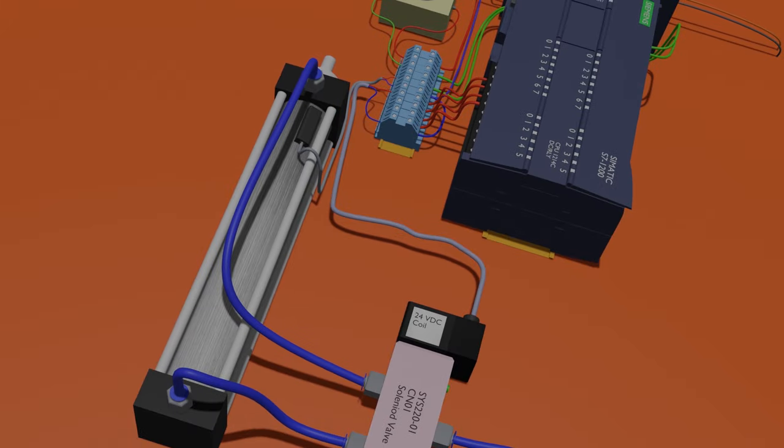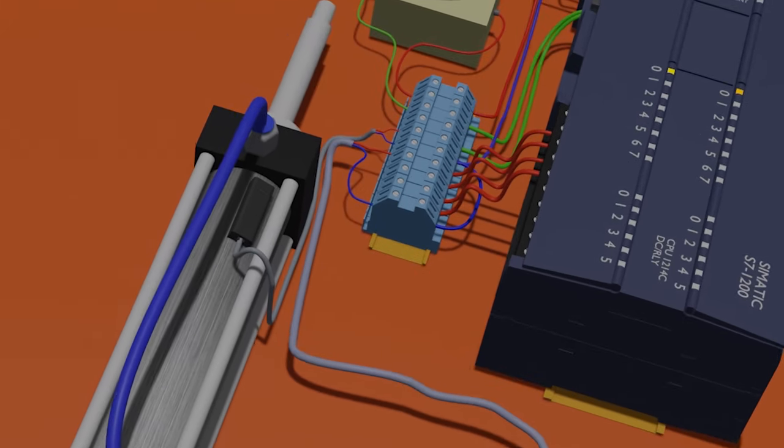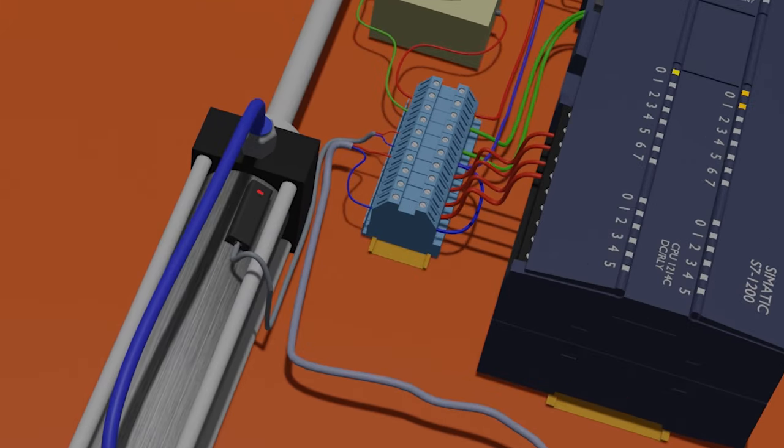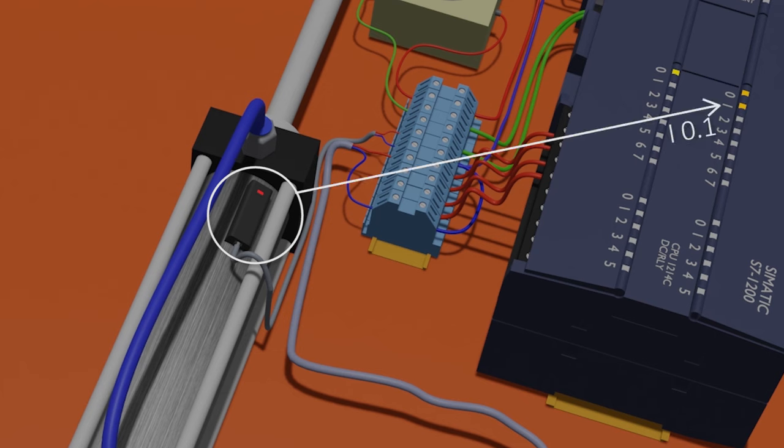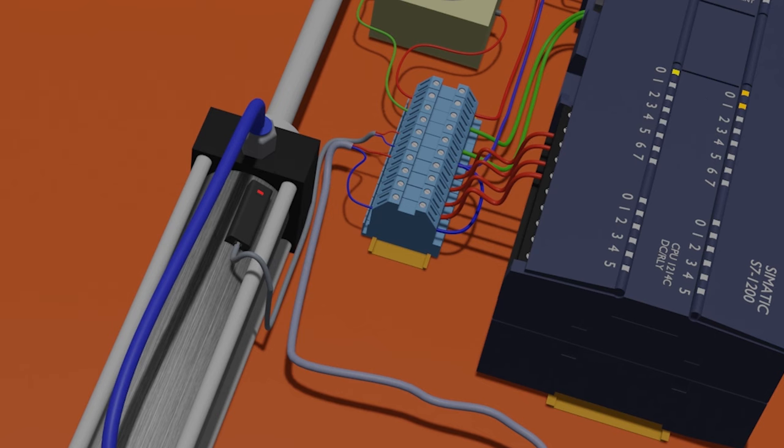We have installed a reed switch on the cylinder body. The output of this reed switch is connected to I0.1 input terminal of the PLC. This reed switch confirms that the cylinder shaft is fully extended outwards and sends a 24 volt signal to the PLC input.